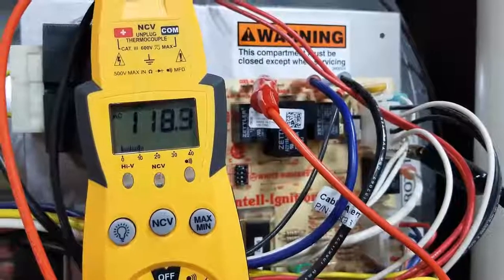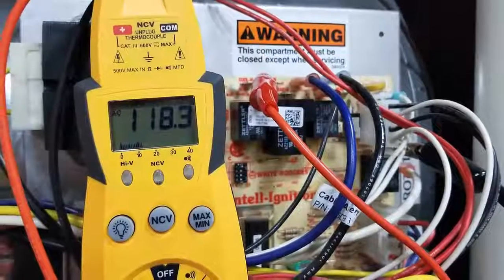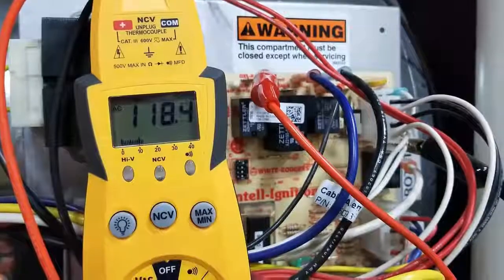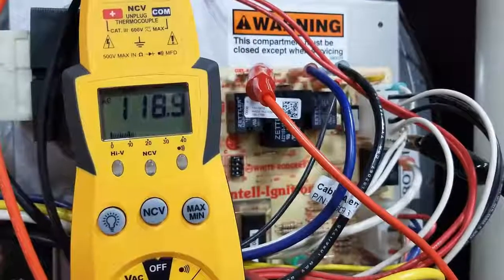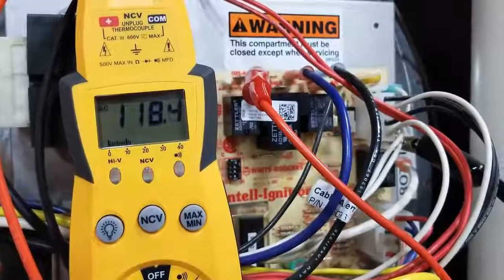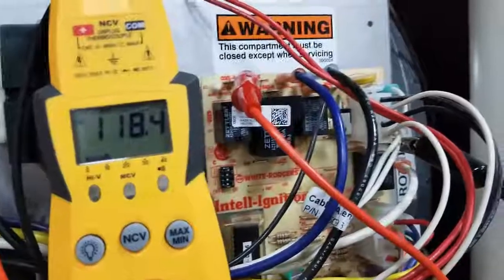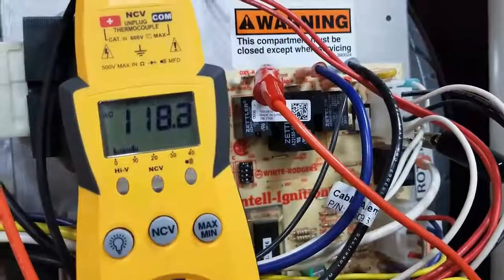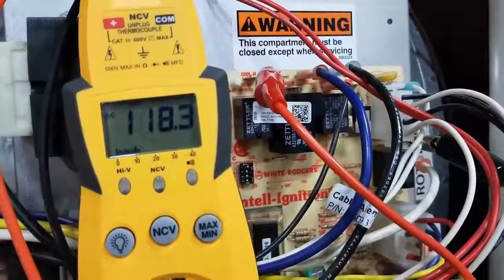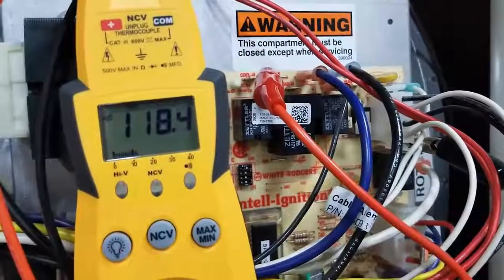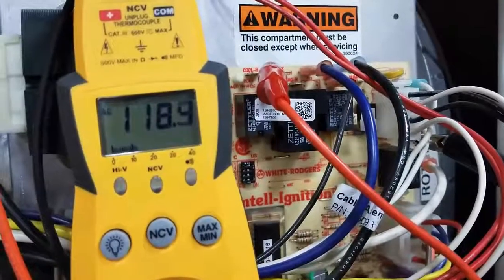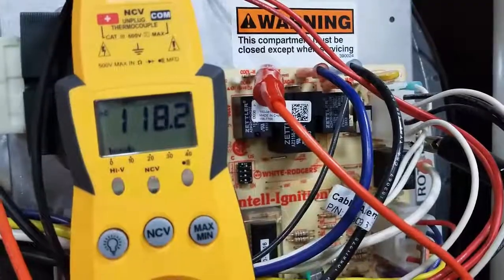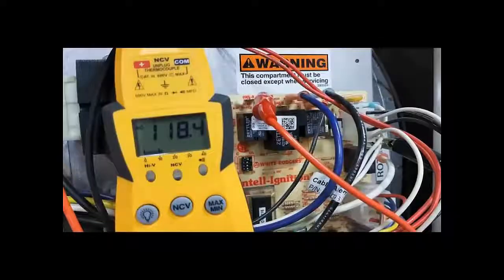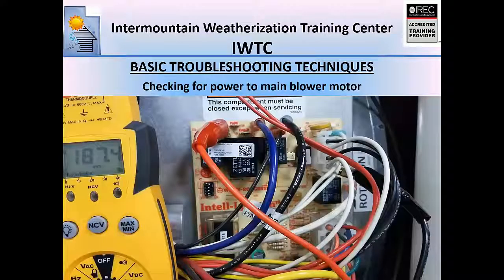And there we go. Showing us we have power from the circuit board to the blower motor. Now if I just let this sit here and run, eventually everything's going to overheat and shut down because I've got the blower motor wires disconnected. But now I know that power is getting, at least from the circuit board, to the wiring to the blower motor. Okay, so that's a real quick and easy way to ensure you're getting power to your blower motor.